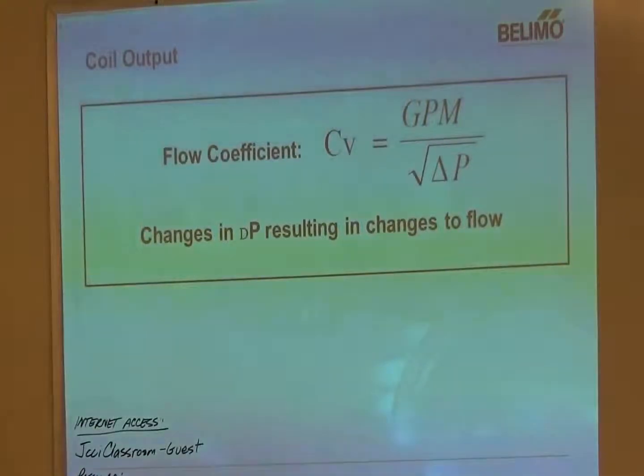A couple different formulas here that I'm sure y'all already know. But the Cv formula, GPM divided by the square root of your delta P, that goes away with pressure independent valves because we're not worried about the differential pressure anymore. So you size pressure independent valves based on your flow. Now I say we don't worry about the differential pressure. We do in some regard.